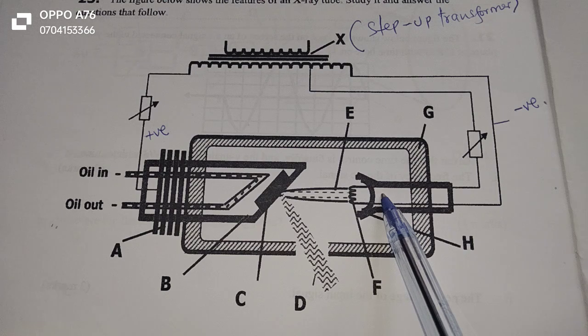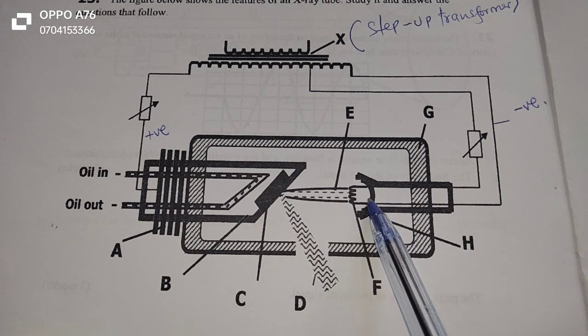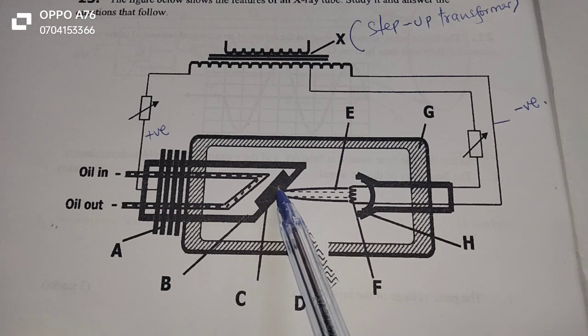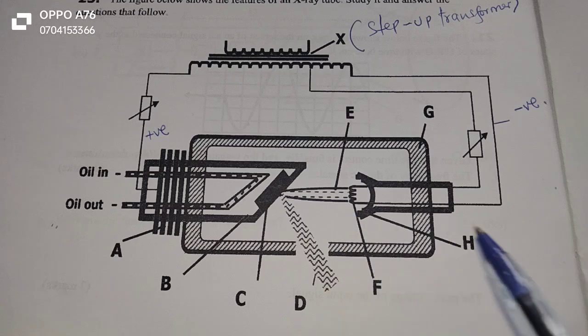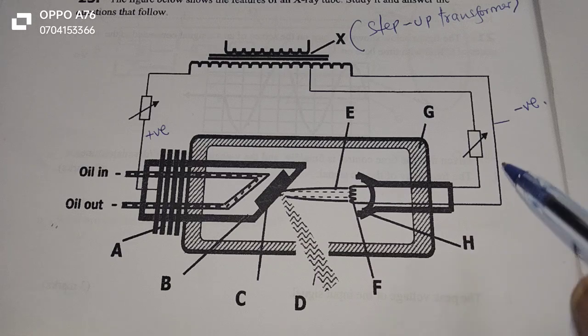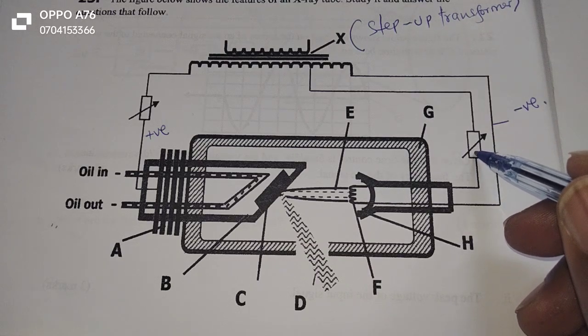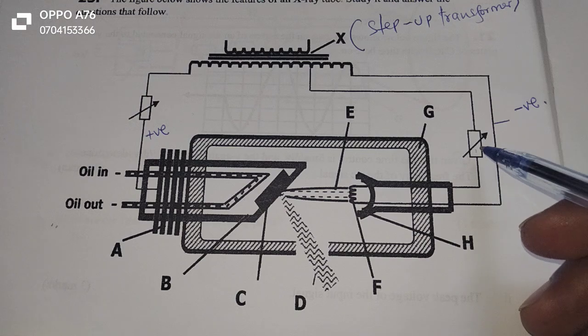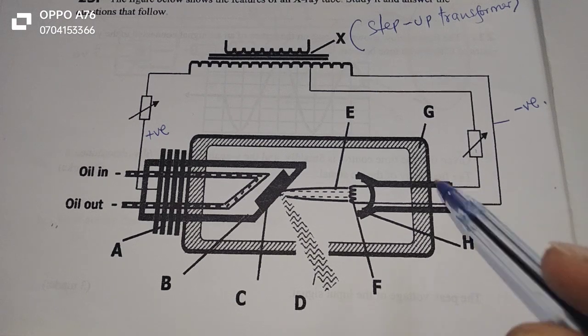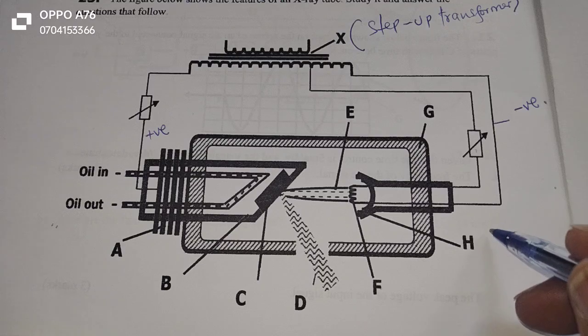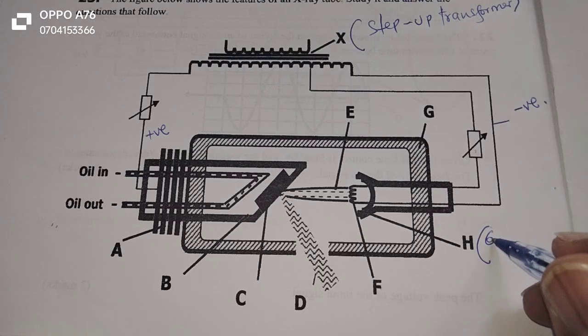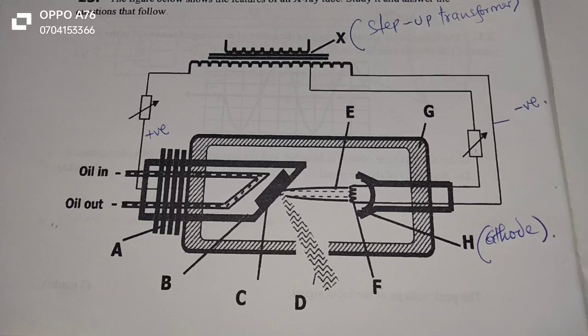This is to ensure that produced electrons are accelerated towards the target here, the target which is attached to the anode. Therefore, briefly to mention about the production of the X-rays, remember this is a rheostat, or simply a variable resistor. It can even be a potentiometer. This resistor is to ensure that current is controlled to the cathode. This one is the cathode.